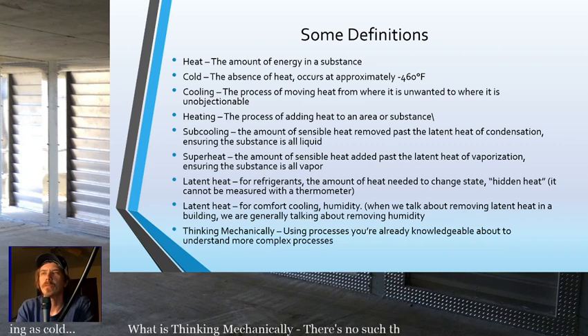Cooling is the process of moving heat from where it is unwanted to where it is unobjectionable. Heating is the process of adding heat to an area or substance. Subcooling is the amount of sensible heat removed past the latent heat of condensation, ensuring the substance is all liquid. Superheat is the amount of sensible heat added past the latent heat of vaporization, ensuring the substance is all vapor. Latent heat for refrigerants is the amount of heat needed to change state, the hidden heat, and it cannot be measured with a thermometer.